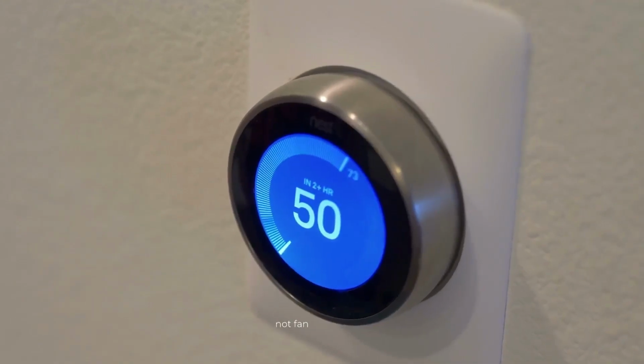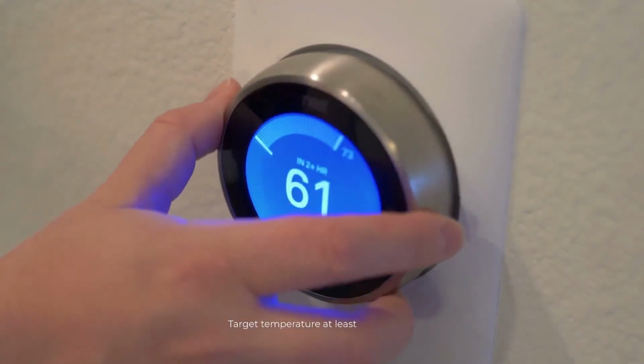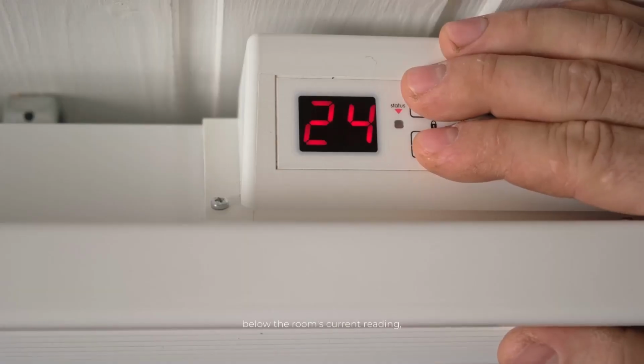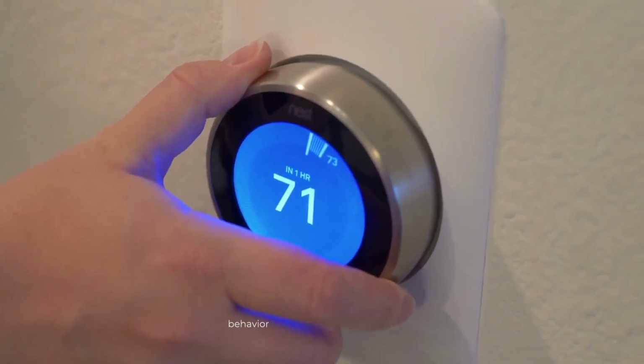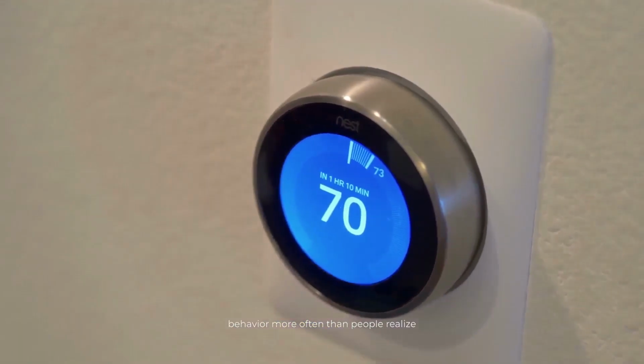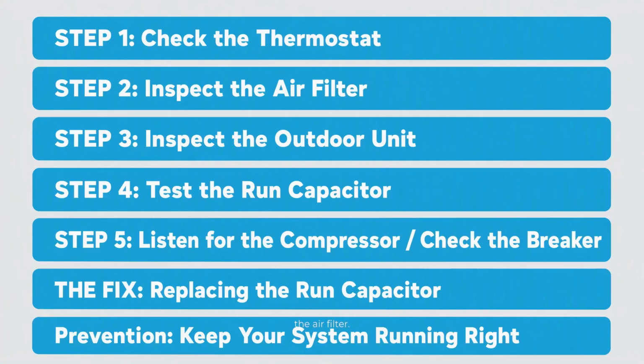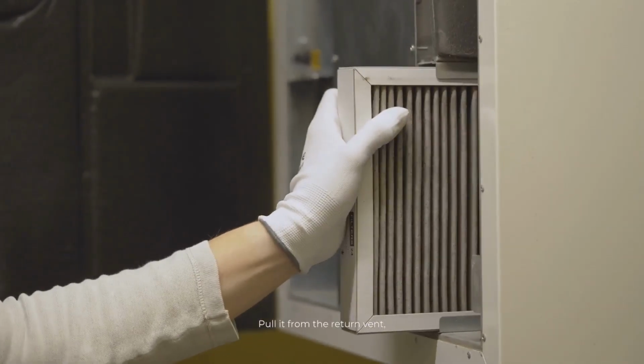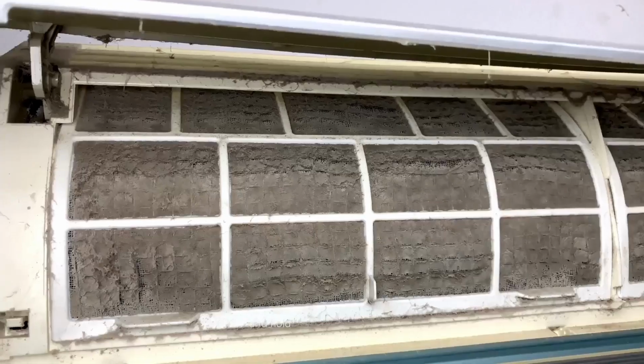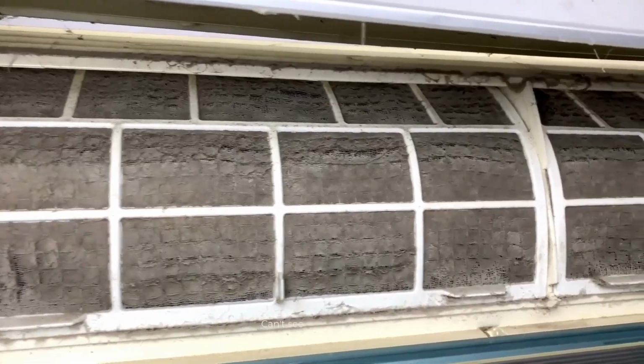Step 1, the thermostat. Confirm it's set to cool, not fan only or heat. Target temperature at least 5 degrees below the room's current reading, and if it runs on batteries, swap them. Weak batteries cause inconsistent behavior more often than people realize. Step 2, the air filter. Pull it from the return vent, usually in a hallway ceiling or wall, and hold it up to a light source. Can't see light through it?